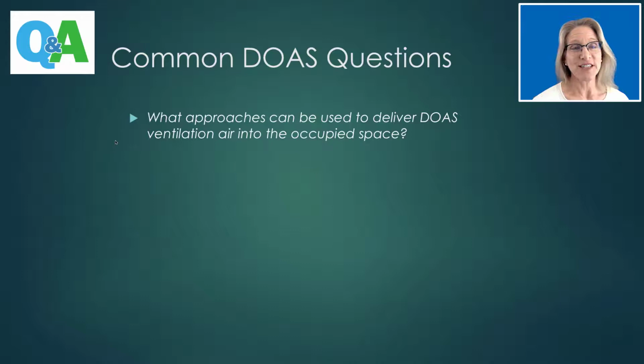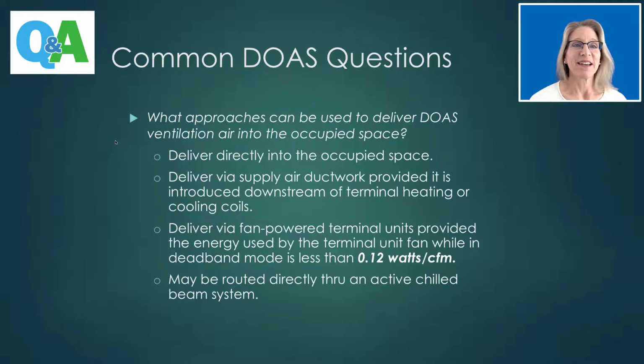Now this question is actually interesting. We've received this question in a variety of different ways. So what approaches can be used to deliver DOAS ventilation air into the occupied space? This was addressed via official interpretation by the State Building Code Council, at least some parts of this. So you can either deliver directly into the occupied space, or you can deliver via the supply ductwork as long as it is introduced downstream of the terminal heating and cooling coils. You can also deliver it via the fan power units or fan power terminal units as long as, when those terminal units are operating during that deadband mode, the fan power does not exceed 0.12 watts per CFM. And then you can also route it directly through an active chilled beam.